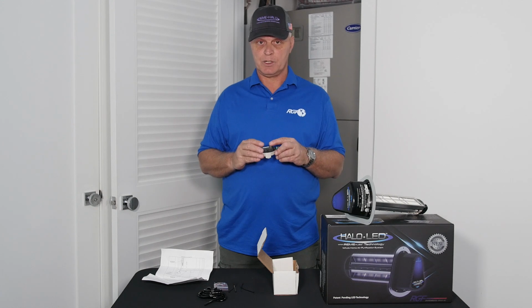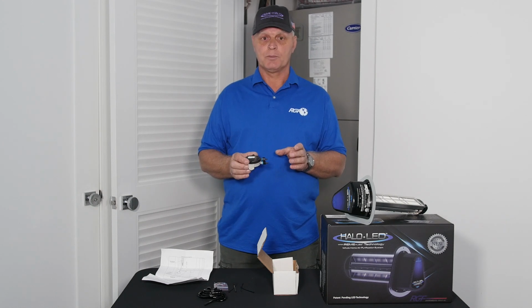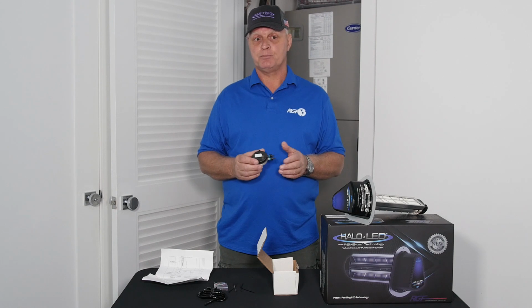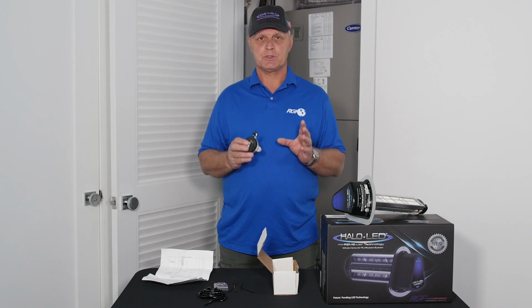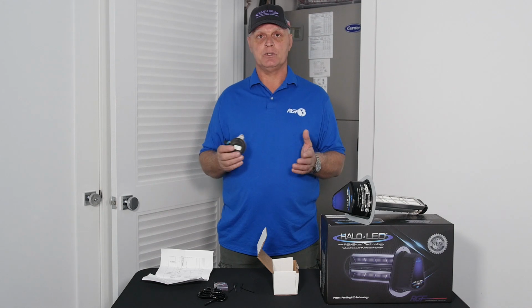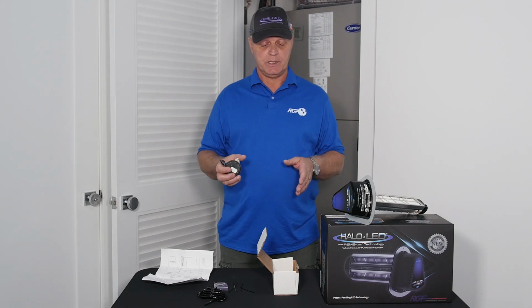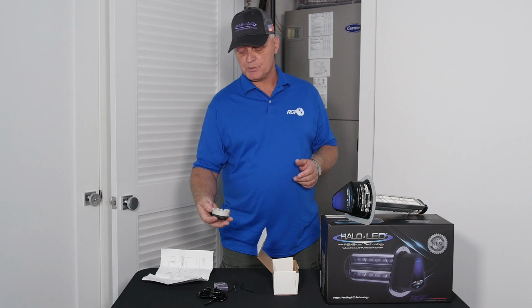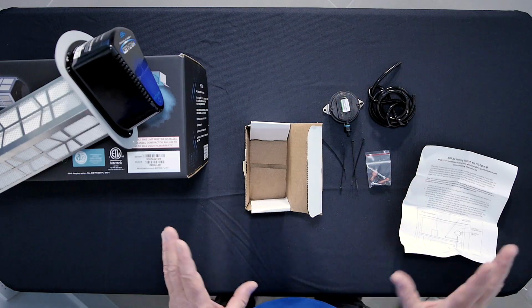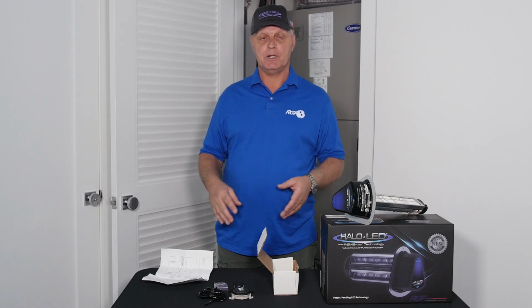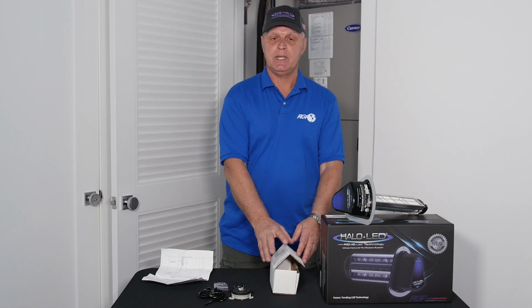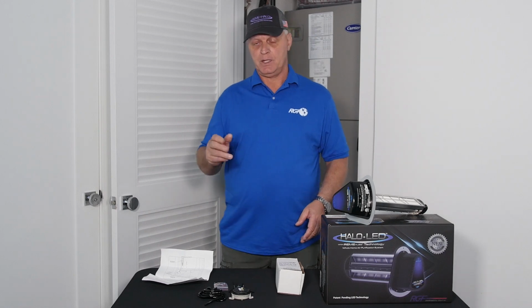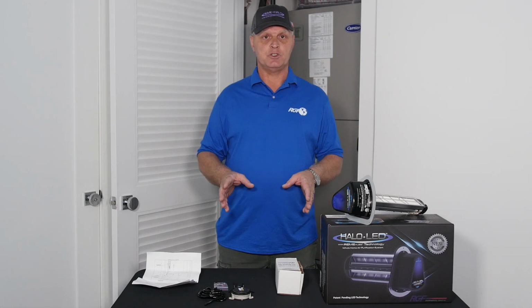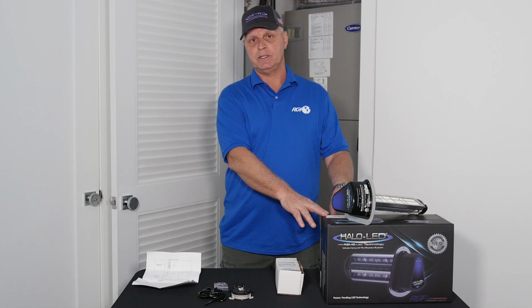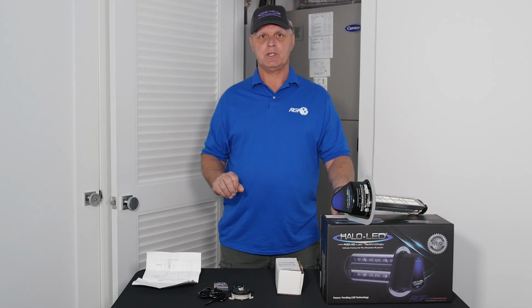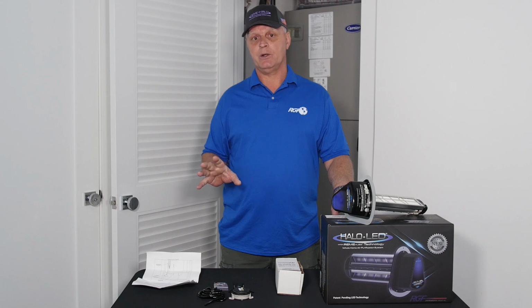The unit has 2 terminals. It is a normally open switch which closes at 0.05 inches of water column, so it will work on any system that you go to install it in. It will work on the communicating systems as well as any other air conditioner that you happen to want to put it on, or a heat pump, or on an electric heat unit, as well as a gas unit. So any unit that you actually plan on installing the Halo-LED in, you can use the air switch and it will simplify your install and your wiring much.